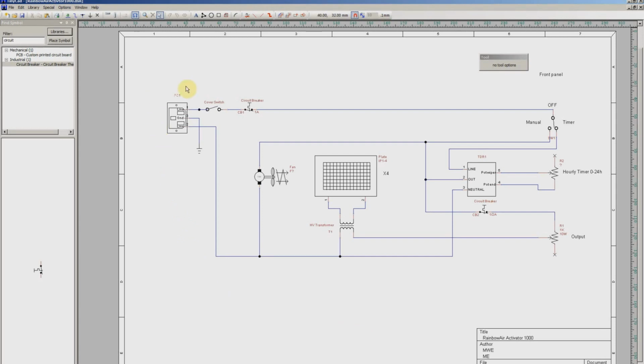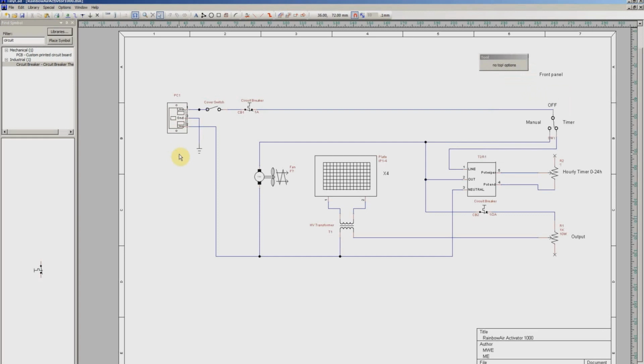Over on the left side up here, we have the line input connector, a standard IEC type connector like you find on computers and other power supplies. The power comes in and goes through the cover switch, the safety switch, kind of an anti-dummy switch, so you don't stick your finger in it and get nastily zapped.